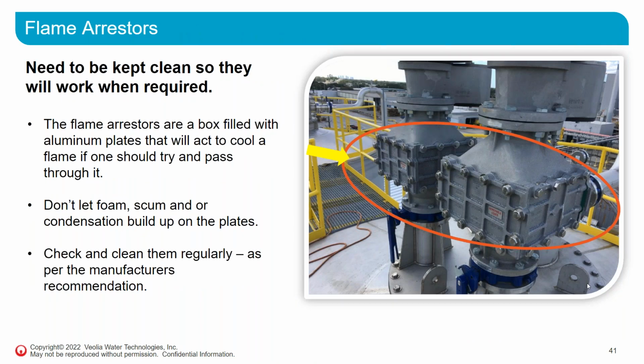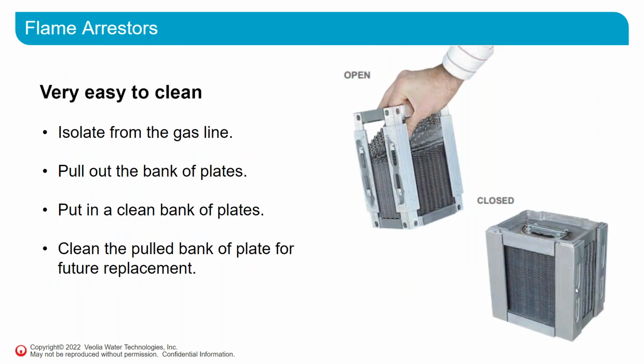Flame arresters are installed in the system. They're a pretty simple design. It's basically a box filled with aluminum plates so that any flaming gas would pass through it and cool rapidly with contact to the aluminum. But if you get foam or scum or water vapor built up in the plates, it prevents the flame from passing through, which could cause issues elsewhere in the line. So it's important to clean and check them regularly as the manufacturer recommends.